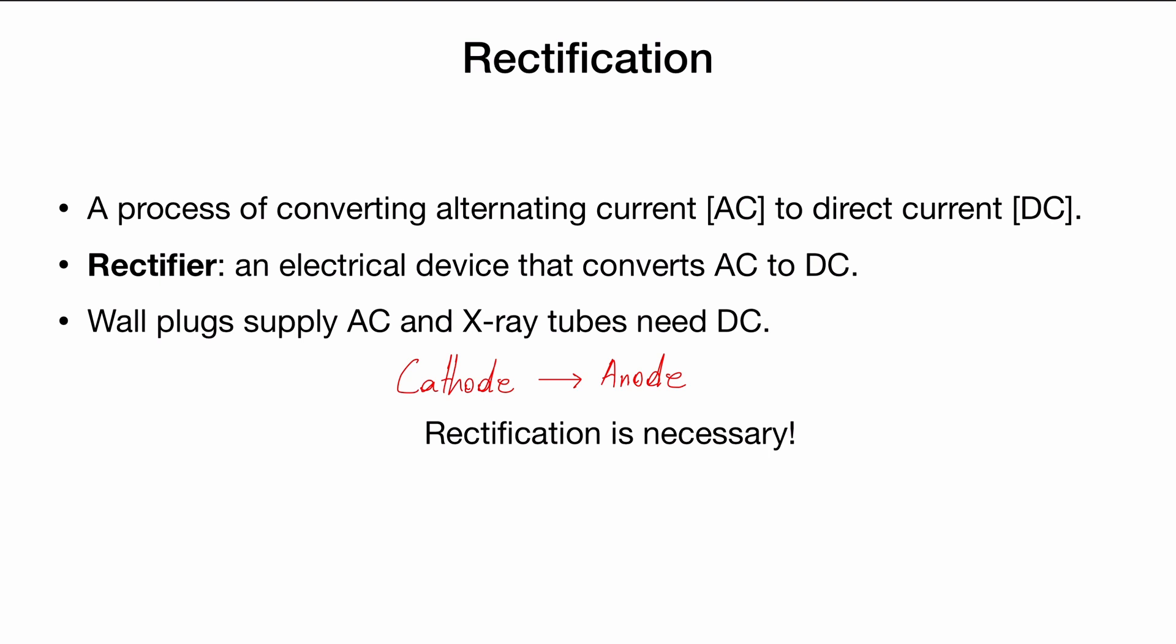However, the way we receive electricity or supply electricity in our hospitals is in the form of an AC, that is current that is going back and forth, current that is alternating its direction. Because of this, we need to have a way of converting the incoming AC from our power source into a DC, which we can use for our X-ray tubes. So the point is, in the context of X-ray tubes, the process of rectification is necessary.